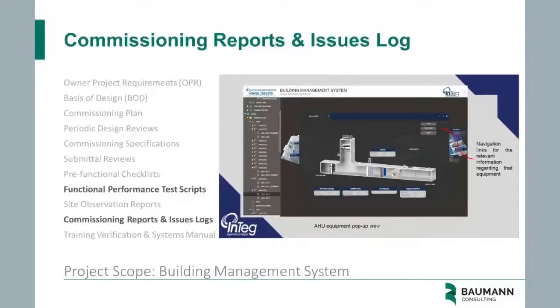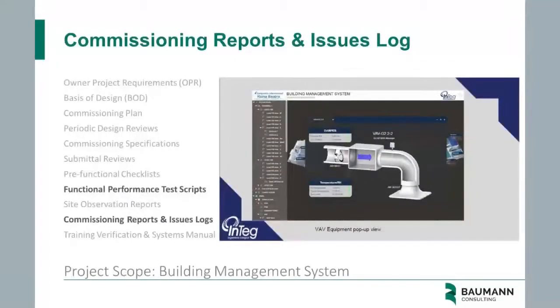So this is a typical AHU, and this is for a typical VAV box. What's shown here basically, it's a variable air volume equipment, so we have damper position on the graphics. We have animations there which show if the damper is going to open or close, how much it's open or closed, depending on half full or half empty, as well as supply temperature from any respective AHUs. AHUs feed these VAV boxes.